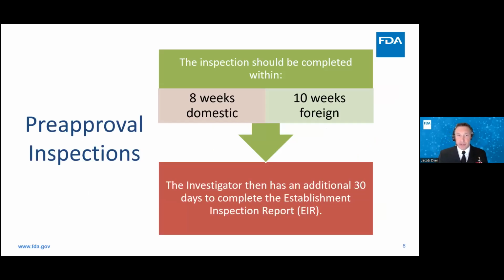So these inspections, from that 30-day mark when a pre-approval inspection is indicated, you're looking at about 8 weeks for domestic and about 10 weeks for foreign for scheduling, and that's the goal. There's always other factors that go in, and as noted before, the facility needs to be ready. Delays in process validations or manufacturer location changes, especially at the last minute, can really delay this time frame.